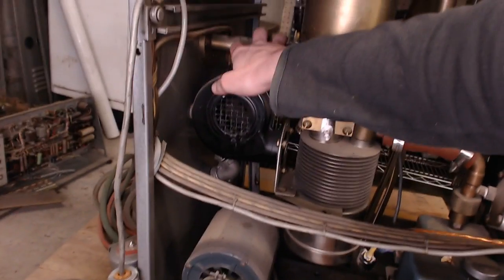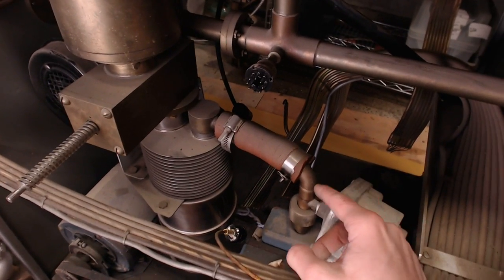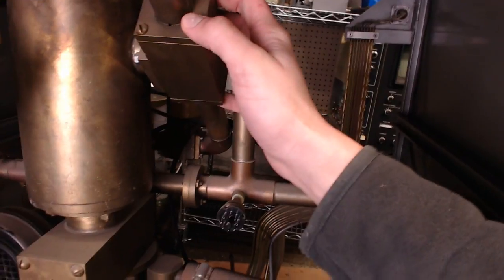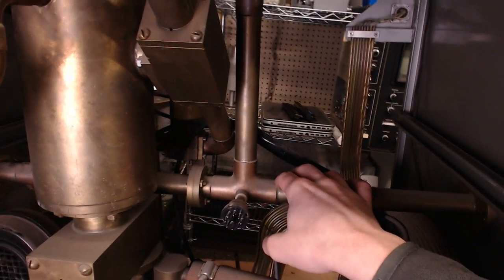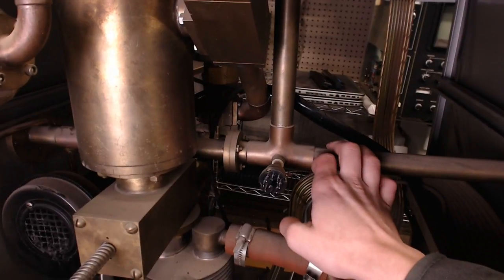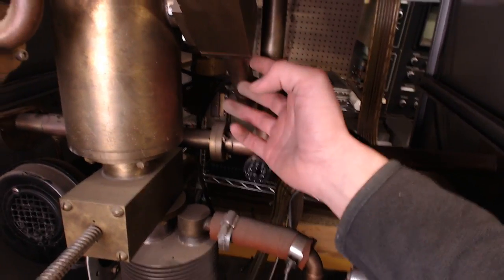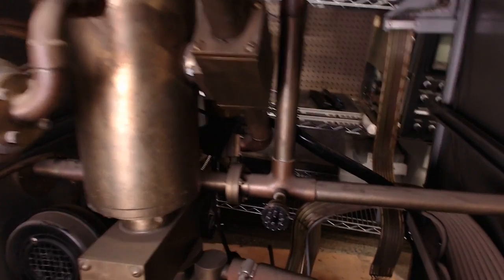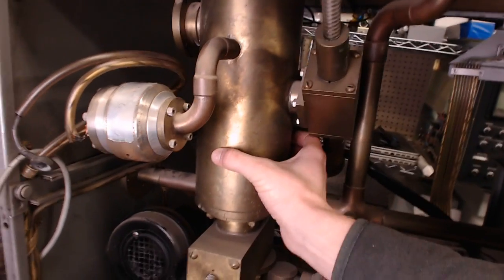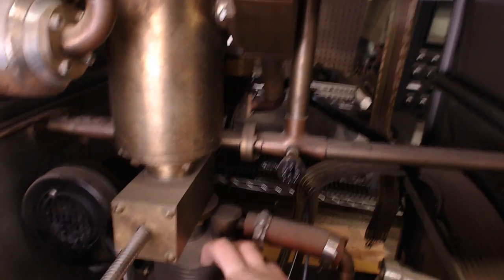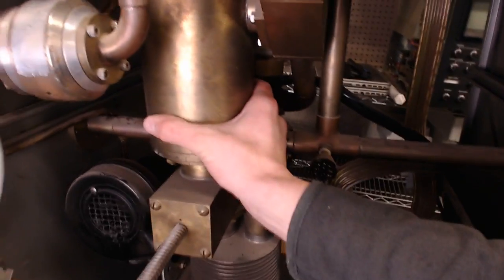And then this entire manifold right here is roughed down with a really big vacuum pump that used to be mounted in the back there, but that big vacuum pump wasn't included in this unit, so it's been adapted somewhere else, I'm sure. And then what happens is through this piece of pipe right here and through this valve, some of the air molecules that are in this roughed down, let's say probably a 50 micron vacuum, are then pulled in through this throttle valve right here, and we'll talk about how the throttle valve works, into this cold trap, and then through this diffusion pump, and then this diffusion pump is backed by this roughing pump. So this is operating at a lot higher vacuum through here.